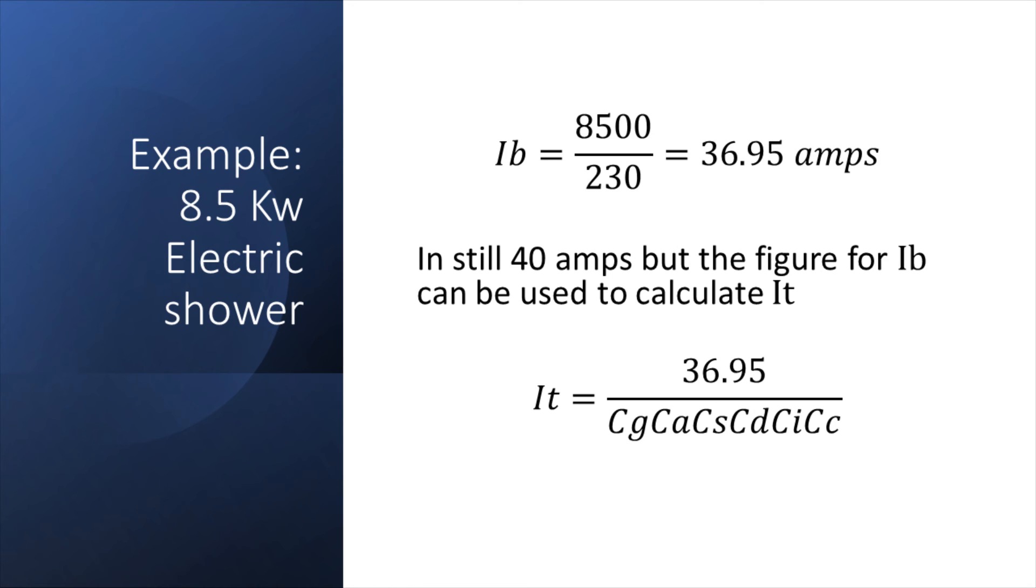In this next example, I've got a calculation for an 8.5 kilowatt electric shower. In the calculation for design current, I've got 8500 divided by 230, which gives us 36.95 amps. In this situation the design current is lower than the protective device. The protective device IN would be 40 amps, but the figure for IB can be used to calculate the IT. So the IT for the cable is equal to 36.95 divided by the correction factors, and that will give us our value for IZ.